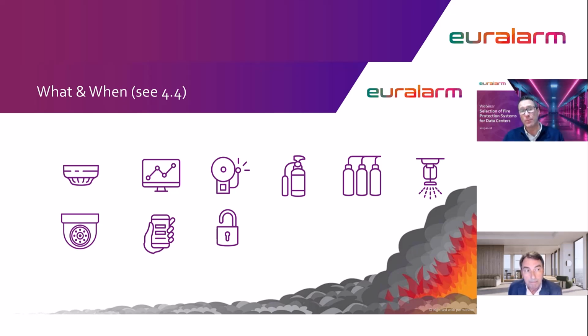I would hope that everybody considering building a data center is doing the very best they can for the environment. Yes, the synthetic agents, when released, will have an effect on the environment. Arguably, the impact of that should be far less than an uncontrolled fire, so we need to bring that into perspective. In some countries, you may not be allowed to have those systems. Throughout Europe now, if you have a 227 and FM200 system, you're able to maintain it, but I'm not aware of us putting in any new systems.